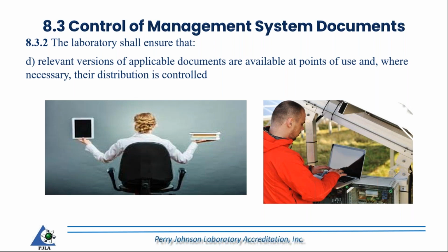I'm a calibration assessor. I'm the calibration program manager. A lot of our labs have technicians going out in the field, going on customer sites and doing calibrations. I often, as an assessor, would like to see them out in the field. Hey, let me see you pull up the procedure that you're using. That's something they should have access to via their laptop or it could be in a binder, but they have to be able to show that they have those documents available to them as required here in 8.3.2D.